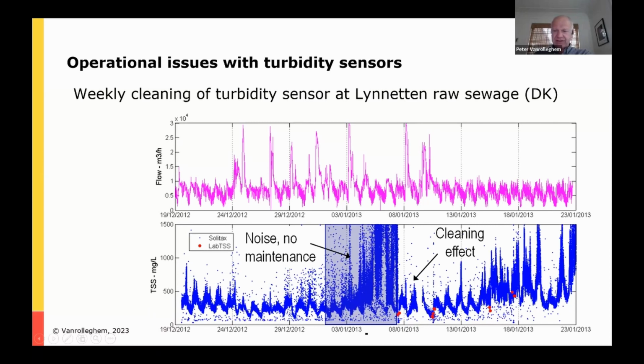You see that the dry weather conditions after New Year led to slowly increasing suspended solids concentrations, which were confirmed by the suspended solids measurements we did in samples. What you see here is the period in which we were on holidays - we didn't go every three days to clean the sensors, and it led to accumulation, drift, and complete failure of the sensor. So cleaning is something that you still need, and you want to minimize it. We will come back to that later.